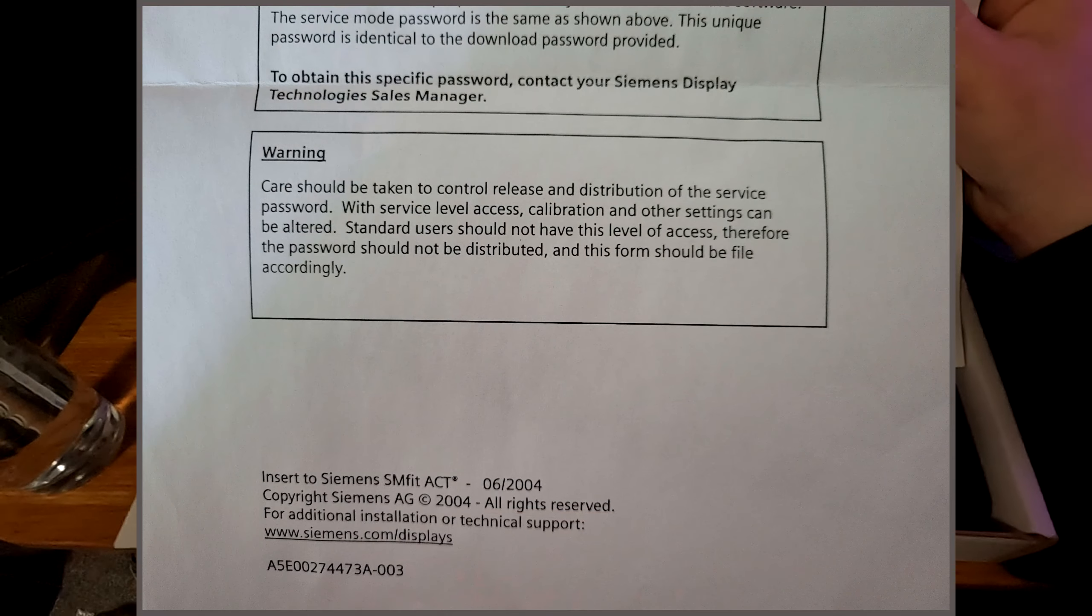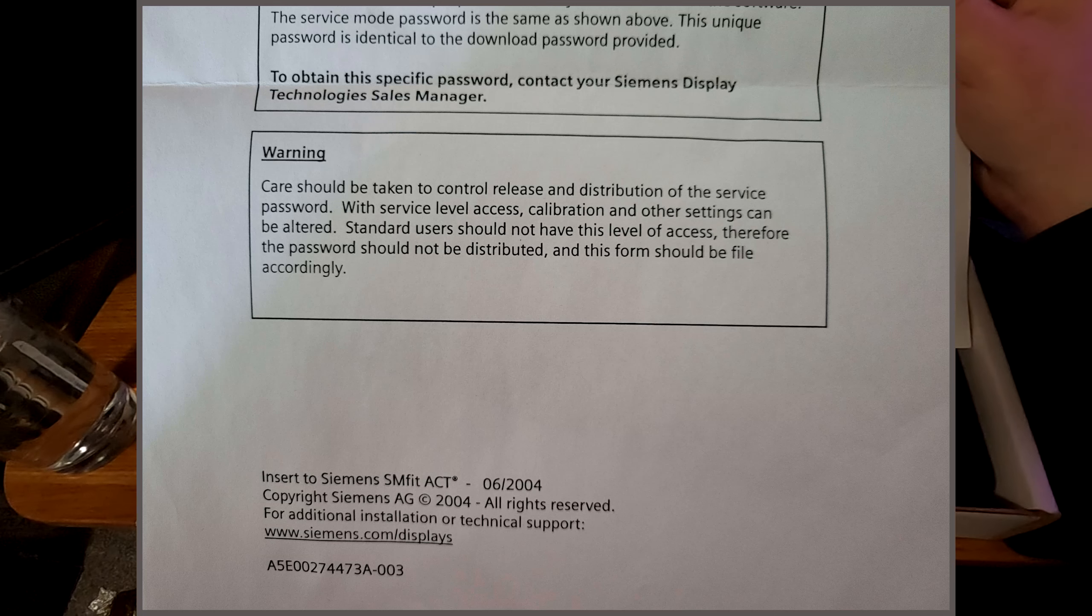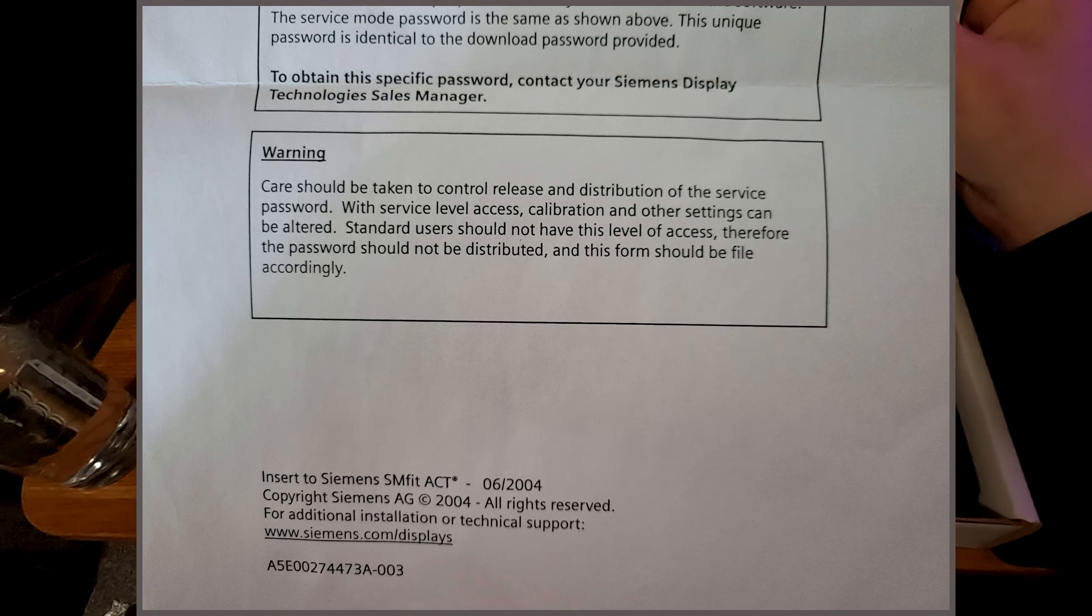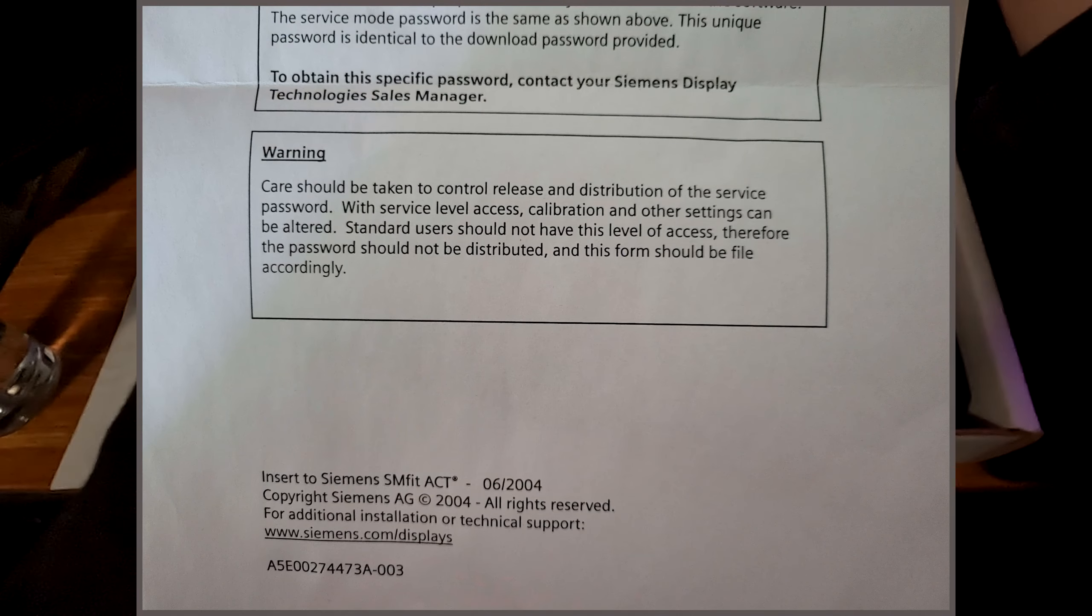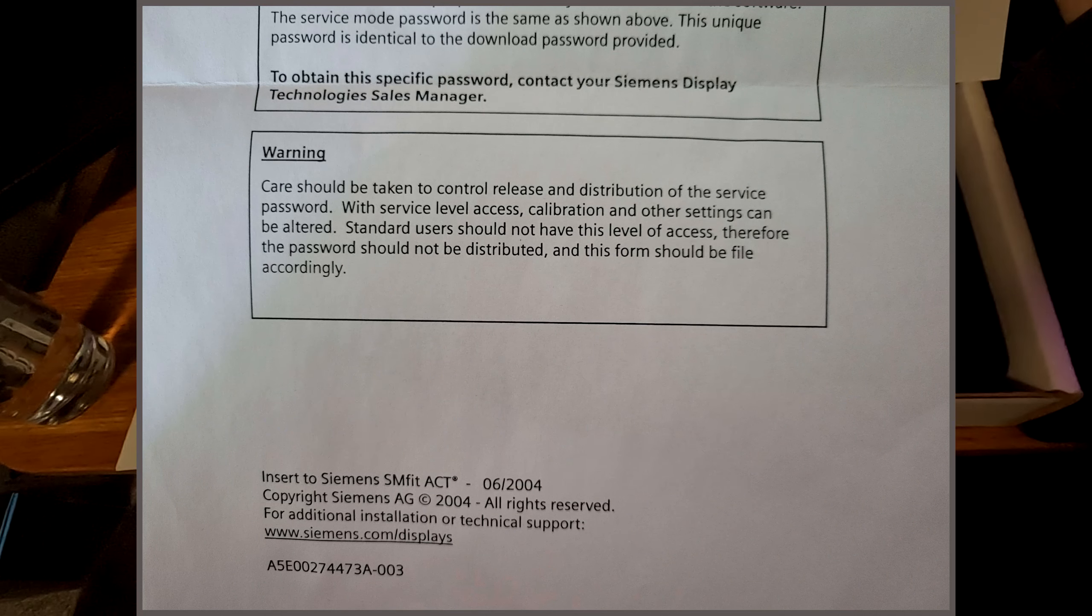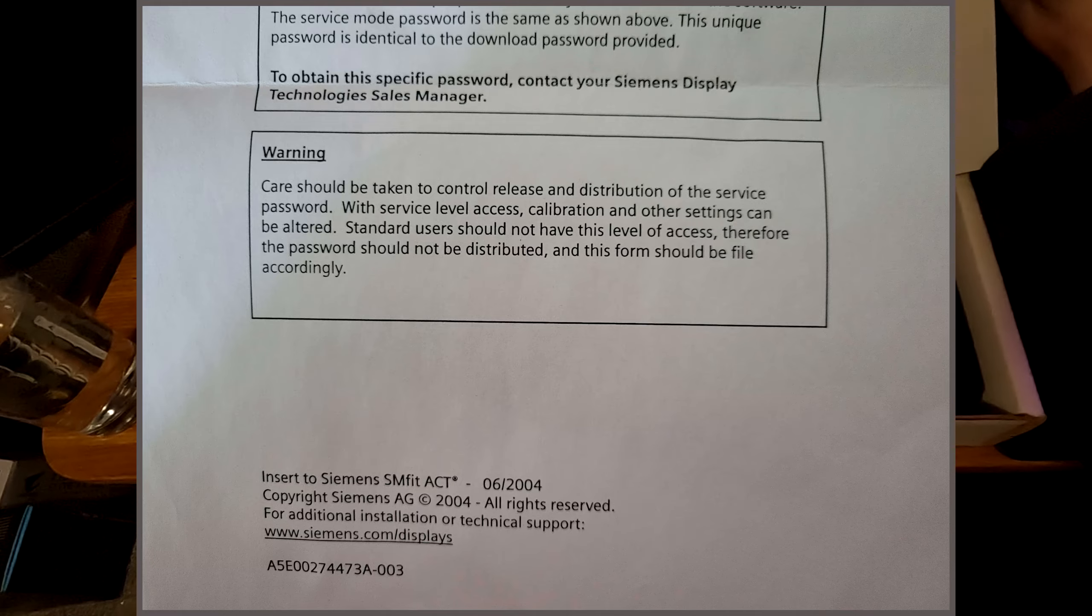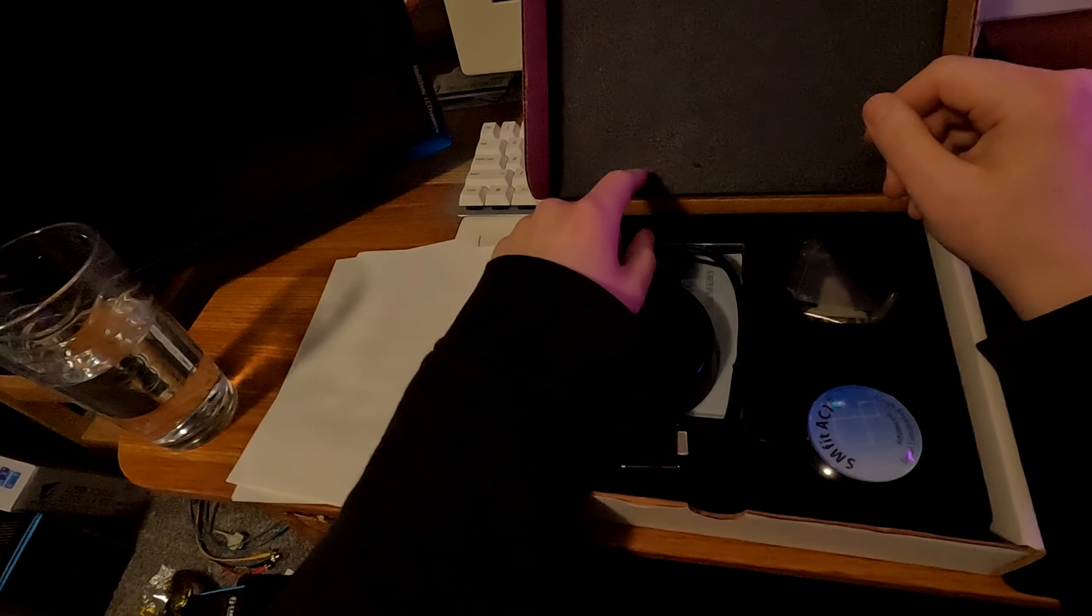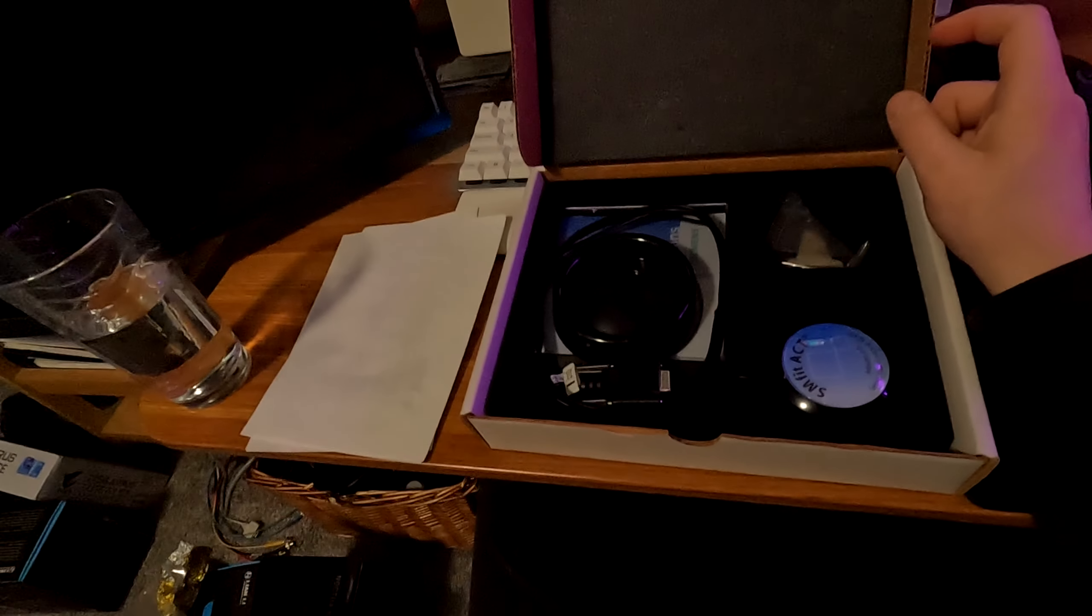Warning. Care should be taken to control release and distribution of the service password. With service level access, calibration and other settings can be altered. Standard users should not have this level of access. Therefore, the password should not be distributed. And this form should be filed accordingly. Insert to Siemens SMfit ACT, June 2004. Copyright Siemens AG 2004. So I guess this copy is from 2004. I think the one that I have that I got from ISO themselves, I believe that one specifically is from 2008.